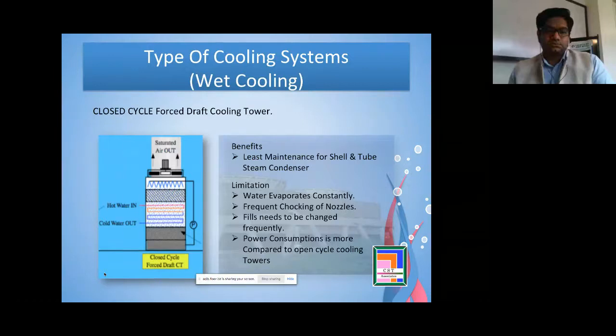So then another one is a closed circuit forced draft cooling tower. In this one, instead of the water going directly exposed to the atmosphere, we have a coil inside, which can be of galvanized steel or stainless steel or whatever material some manufacturers use, and basically it is a closed loop. On one side the shell and tube heat exchanger is there, and the pump is there. The water flows inside the heat exchanger, and the water inside the cooling tower is drawn by a pump, then sprays over the closed circuit heat exchanger, and it cools the water.